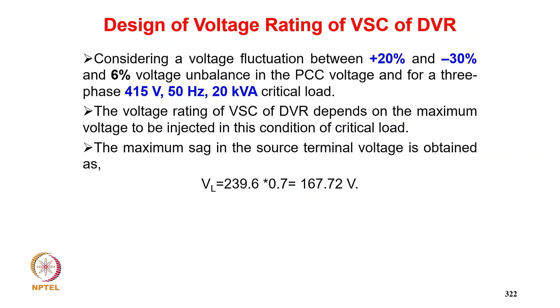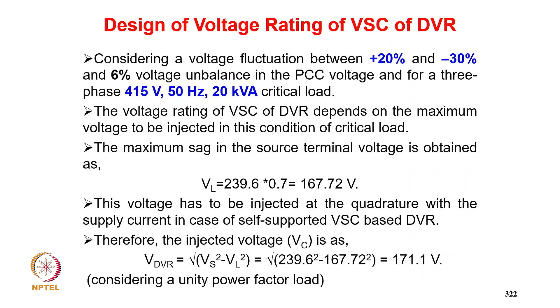Considering voltage fluctuations between plus 20%, minus 30% and 6% voltage imbalance in a 3-phase 415 volt 50 Hz 20 kVA critical load, the voltage rating of the VSC of DVR depends upon the maximum voltage to be injected in this condition of critical load. The maximum sag in the source terminal voltage gives VL equal to 239.6 into 0.7, that is 167.72 volt. This voltage has to be injected in quadrature with the supply current in the self-supported VSC of DVR. Therefore, the injected voltage VDVR equals root of VS square minus VL square, and putting the values it comes to 171.1 volt, considering the unity power factor of load.